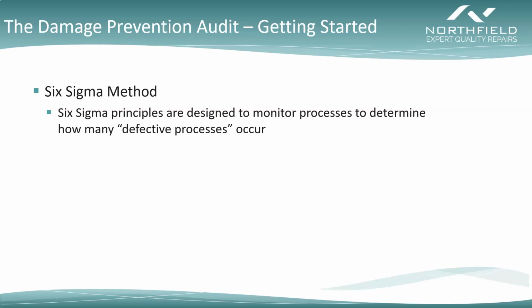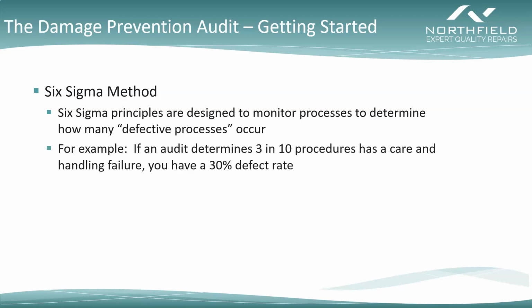So if you think about reprocessing a scope, you think about what a perfect process would look like, meaning nobody made any mistakes at any point throughout it. And we want to determine how many times this process is defective, meaning there's a mistake being made. So, for example, if we audit this and determine that out of every 10 procedures, 3 of them have a care and handling failure, you have a 30% defect rate. And I would suggest that probably for the most part, we're going to see significantly higher numbers than that.